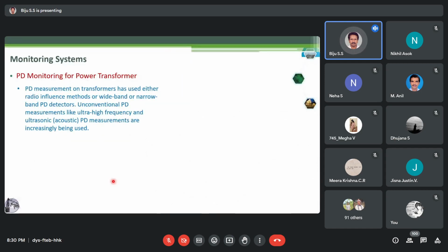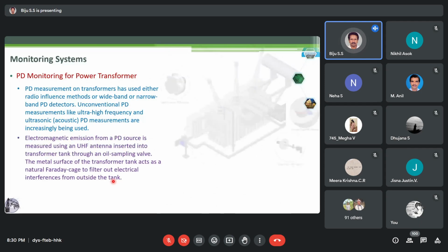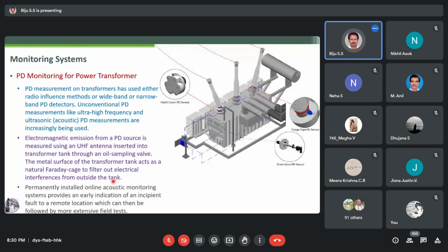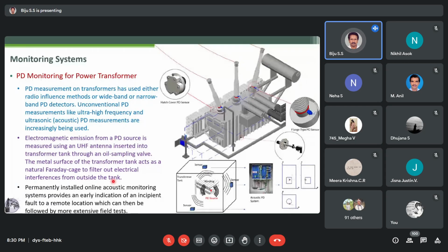It's a PD monitoring for transformer. In early days we used to have radio influence methods of wideband and narrowband PD detectors, but nowadays we are going for ultrasonic detectors, acoustic detectors, which is more accurate, and it's a very good installation for giving out the condition of the transformers. Because PD is often present well in advance of insulation failure. Therefore, monitoring partial discharge will give you a good indication of the defects or deterioration in transformers.